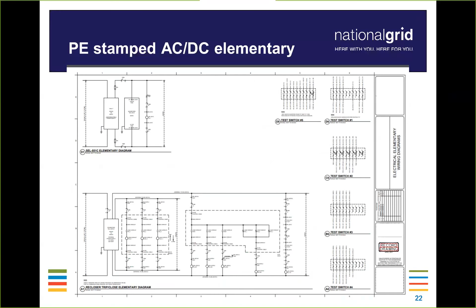Yes. So this would only hold true on an AC or DC elementary if you have some kind of logic function outside of what's encompassed inside of your inverter. If you had some kind of a relay, for example, we would be interested in the ladder logic diagrams showing us the inputs and outputs of the relay, their associated functions, and the test switches which are connected to that relay for isolation and testing. So really that's going to give us a picture of any logic functions that are being processed with a protective relay.